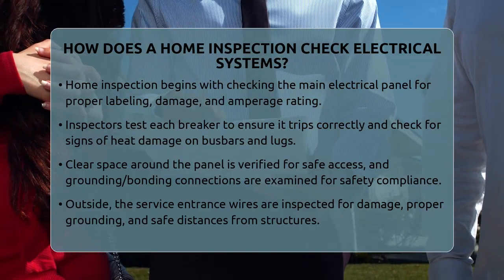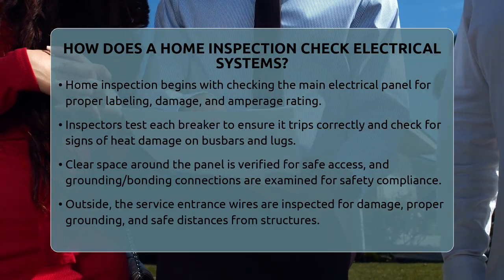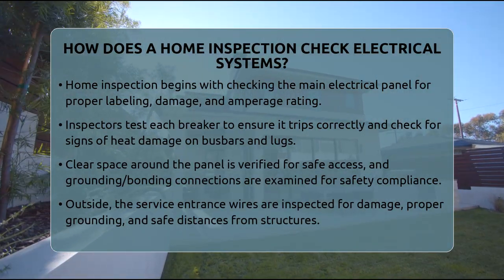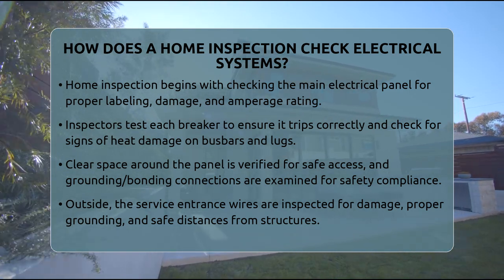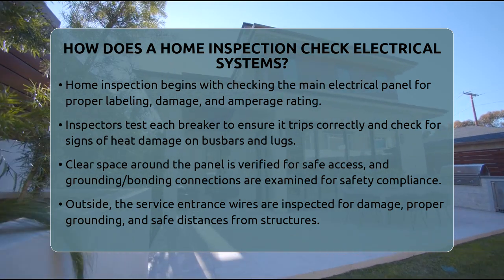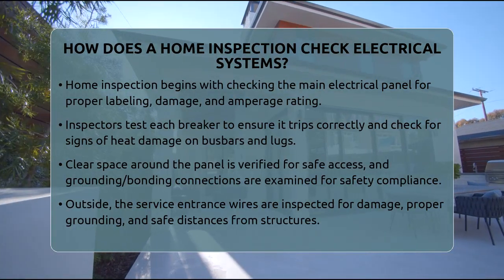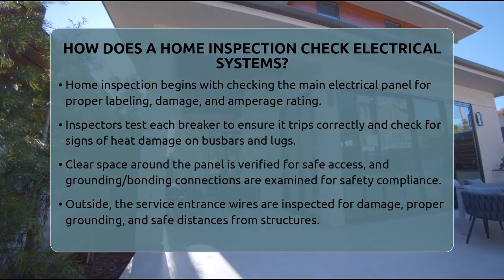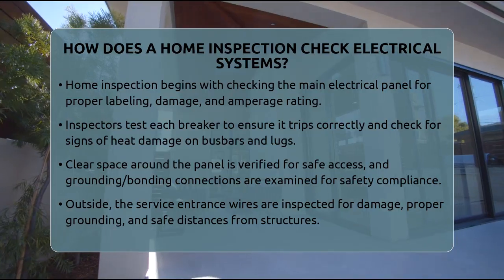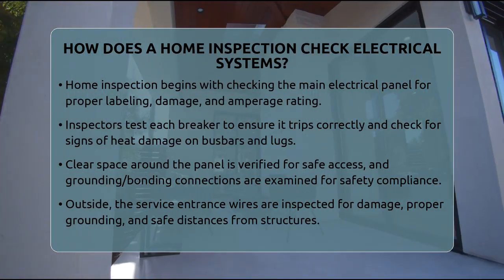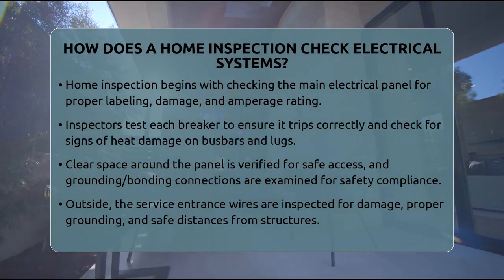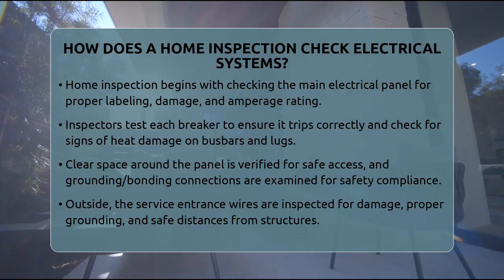They look at the amperage rating, which tells you how much electricity the system can handle. The inspector makes sure the panel is properly labeled so you know which breaker controls each circuit. They check for rust, heat marks, or any visible damage that could signal trouble. Each breaker is tested to see if it trips properly when overloaded or shorted, which helps prevent fires.